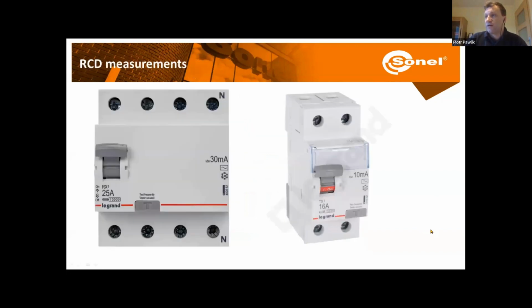Now, before we start this measurement, we need to auto-zero the test leads. So to get rid of resistance of the test leads, well, I mean, you can imagine that sometimes when you go from main grounding rail to different sockets, it could be a longer distances. So we don't want to measure the resistance of our test leads, just the resistance of the wire in the wall.